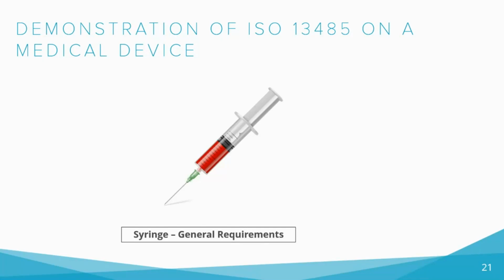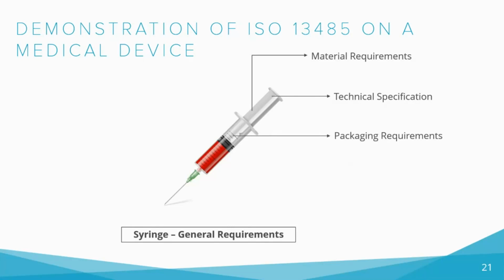I would like to show a few requirements which are general requirements for a medical device. For example, any given product should have material requirements where we select certain material which suits best for its purpose. Considering medical devices, material should be biocompatible and shouldn't pose any side effects. One should have defined technical specifications of the product, like inputs, outputs, verification criteria, validation criteria, design transfer, assembling plan, etc. We should have specified packaging and storing requirements defined depending on the nature of the product and its marketing. Product should be appropriately packed and stored so that its performance, functionality, or sterility is not compromised.